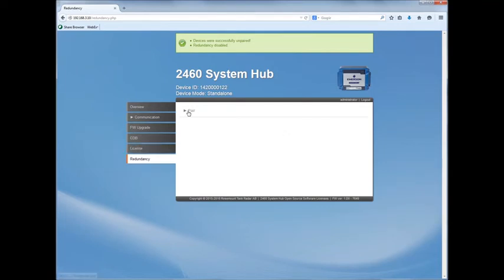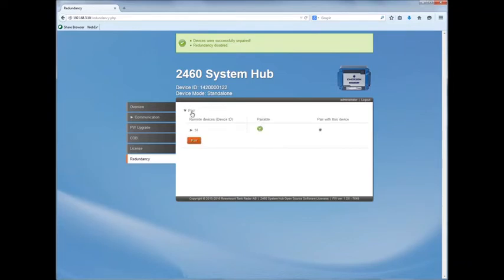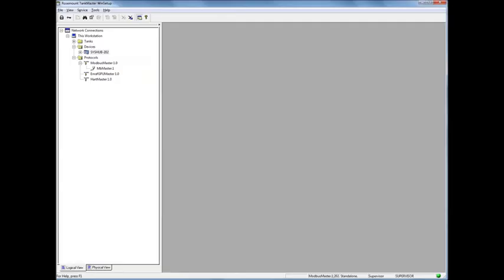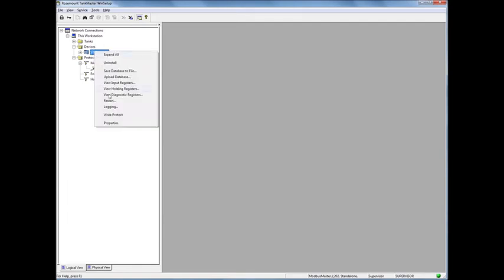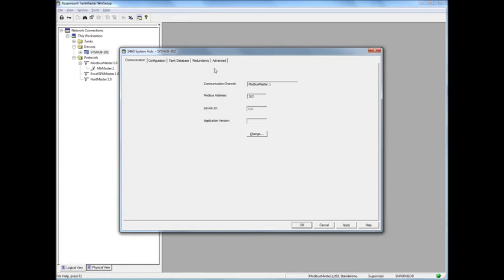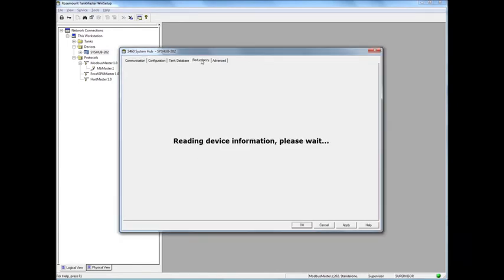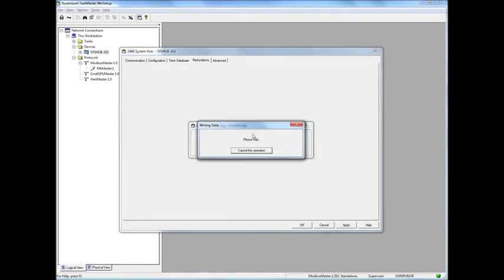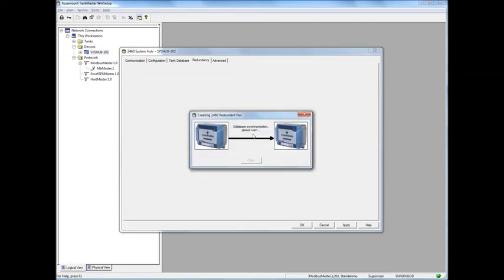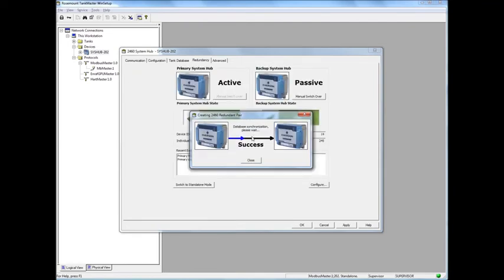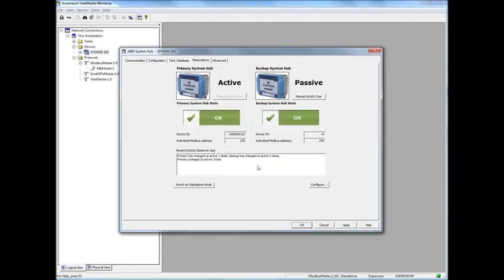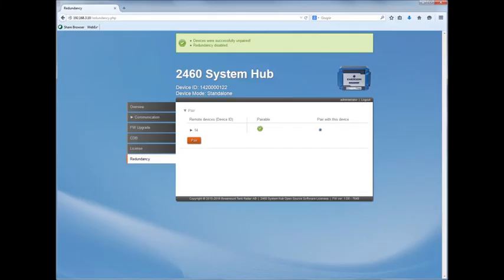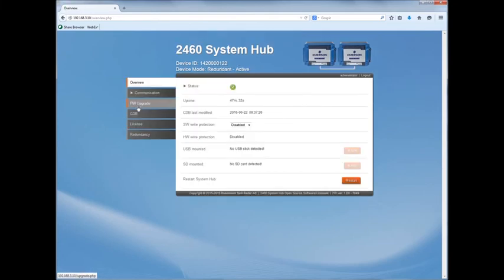We have a connection to the new backup unit, so we go to Pair. To enable redundancy with the new unit, we go back to TankMaster and do the same as we did the first time. We go to Redundancy tab and push Create New Pair. The system is now linking together and the databases are synchronized. And we have a new redundant pair with the replaced unit.